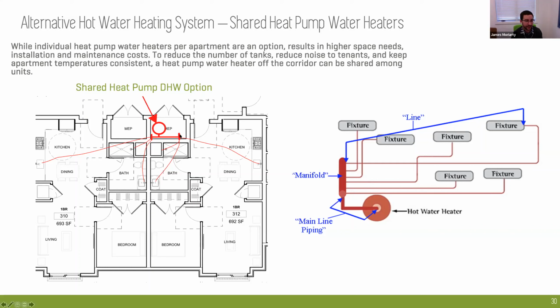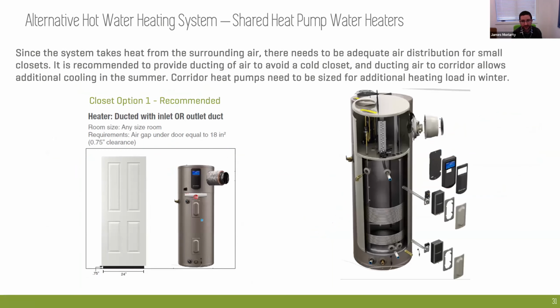I think we've seen an 80-gallon tank used for 4 apartments. So that's a possibility as well. When designing around shared heat pump water heaters, definitely make sure there's enough air transfer, because you're stealing heat from inside the building. That's why the corridor becomes a decent sink for that, because it gives the corridor free cooling all summer. And then in the winter, you would need to make sure you're sizing the heat pumps for the corridors to make up for that.